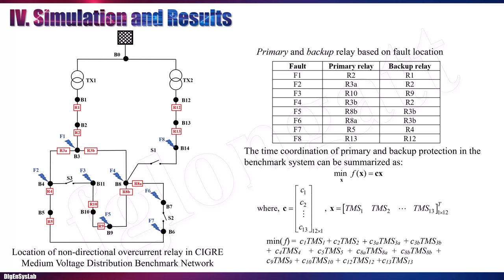For the simulations and results presented here, switches S1, S2, and S3 are open. The circuit breakers and corresponding relays R1, R2, and so on are indicated in red. The relays located in both feeders must fulfill primary protection and also offer backup. In this table, you can see who provides primary protection and who offers backup, and we formulate the problem of minimizing the total time coordination.